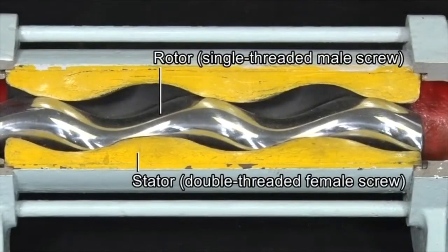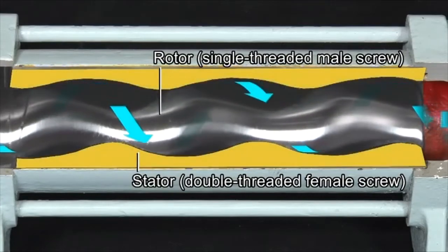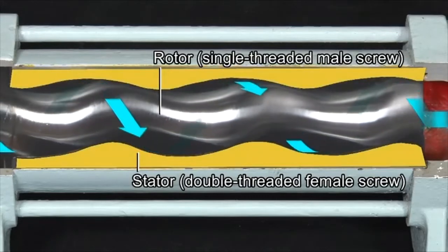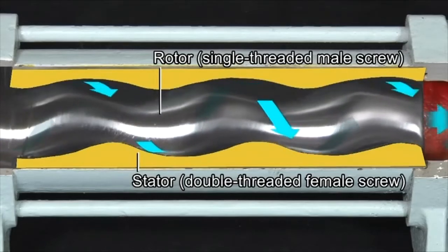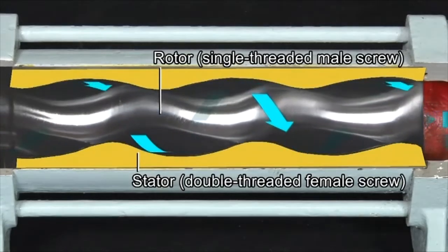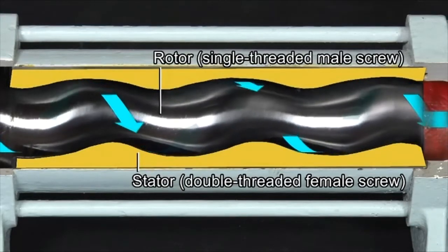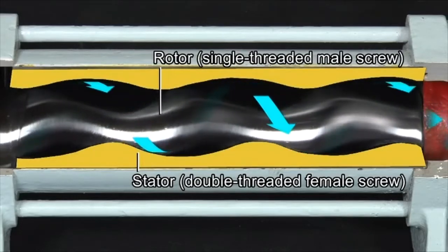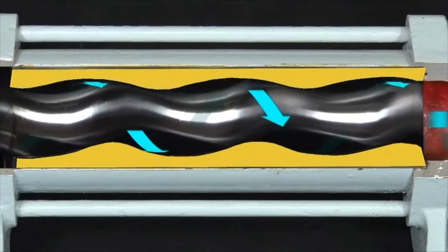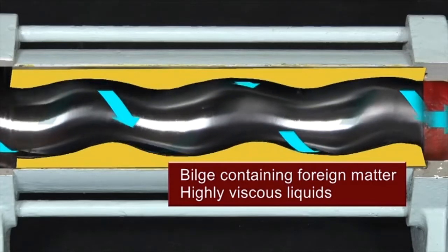The one screw pump is a kind of displacement screw pump and consists of a stator and rotor. If the rotor of a single threaded male screw is turned inside a double threaded female screw stator, the rotor turns inside the stator. The stator is made of a flexible material and the rotor continuously moves from one space to another as produced between the rotor and stator. This is how pump action occurs and its continuous movement transfers bilge containing foreign matter as well as viscous liquids.